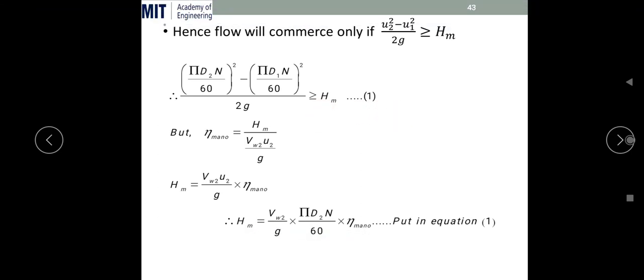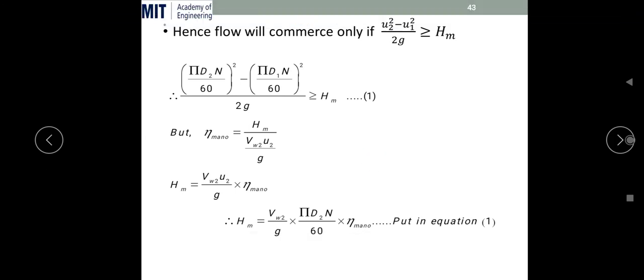Now we substitute for the manometric head. We know that manometric efficiency η_m = H_m / (Vw2·u₂/g), meaning manometric head divided by work input per unit weight. So H_m = Vw2·u₂·η_m/g. Substituting u₂ = πD₂N/60, we get H_m = Vw2·(πD₂N/60)·η_m/g.